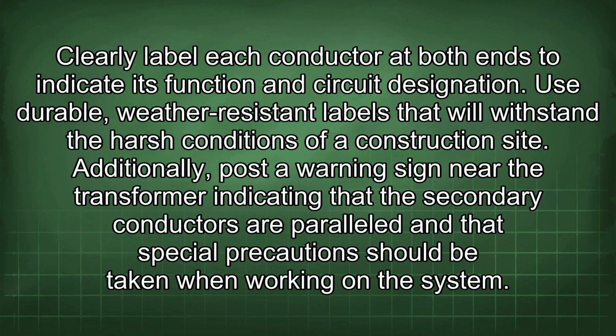Clearly label each conductor at both ends to indicate its function and circuit designation. Use durable, weather-resistant labels that will withstand the harsh conditions of a construction site. Additionally, post a warning sign near the transformer indicating that the secondary conductors are paralleled and that special precautions should be taken when working on the system.